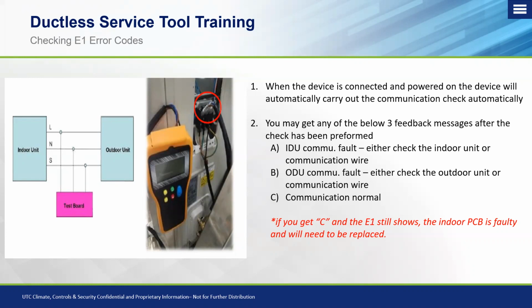Again, this is not to say that as soon as you get an indoor communication fault or outdoor communication fault, you just replace the board. We still need to be service techs. We still need to do our due diligence and troubleshoot through the situation to make sure that it's something not external to the board, so if the board does get replaced, we're not back out there with the same issue again. But as a rule of thumb, this is how we're going to do a basic communication check to make sure that the system is operating properly. Or if we're on a service call, this is how we're going to confirm where that actual E1 is present.